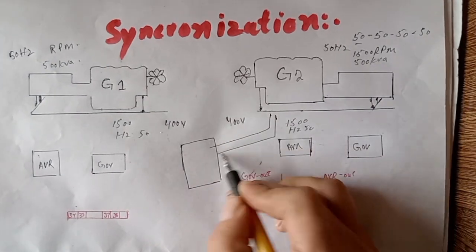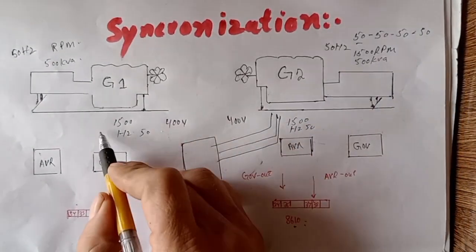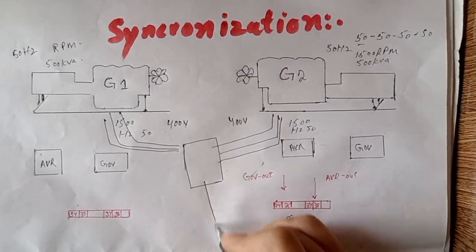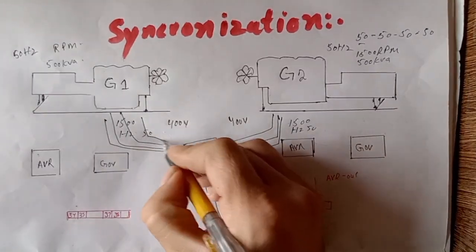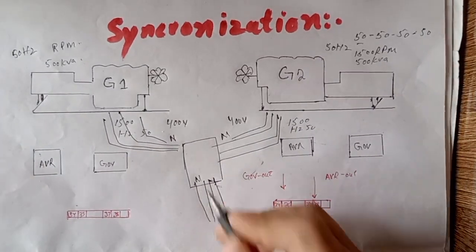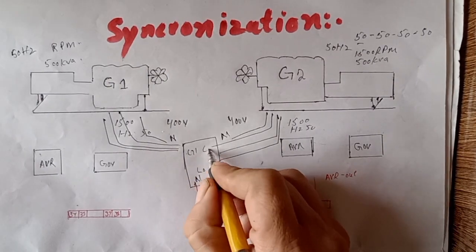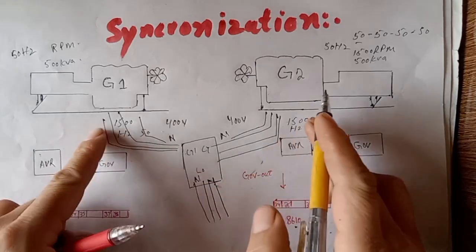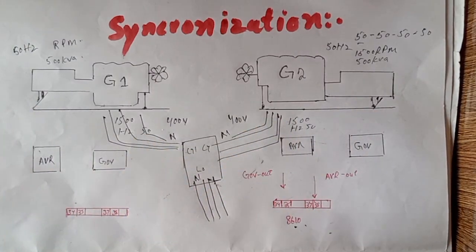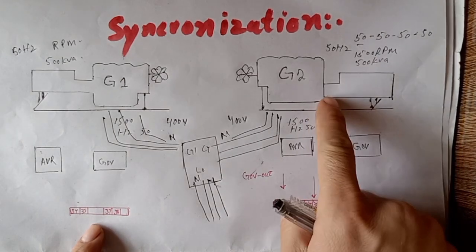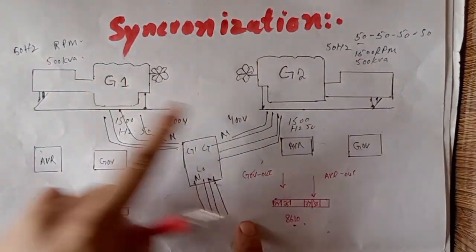Take the three phases from generator one and also three phases from generator two. This is our bus bar going to load — three phases and neutral from each generator. Match all ratings, frequency, and RPM of both generators. Install one DFC controller model 8610 on each generator. All frequency, voltage, and rating parameters must be the same for both generators.